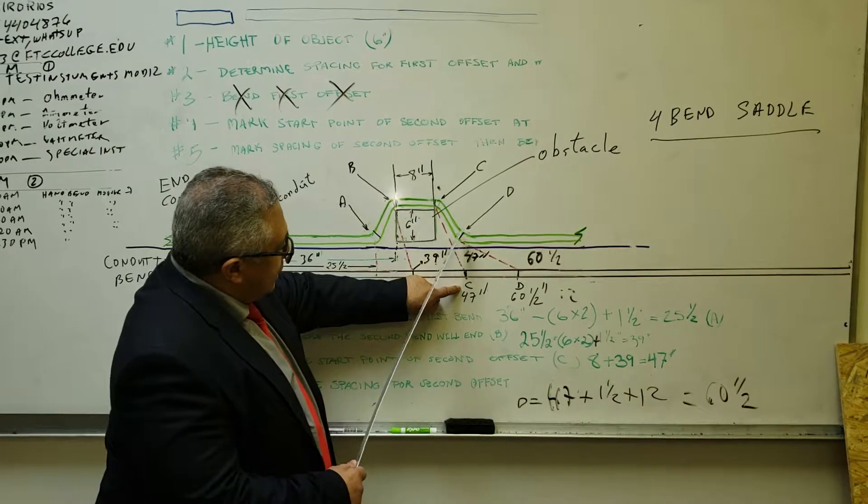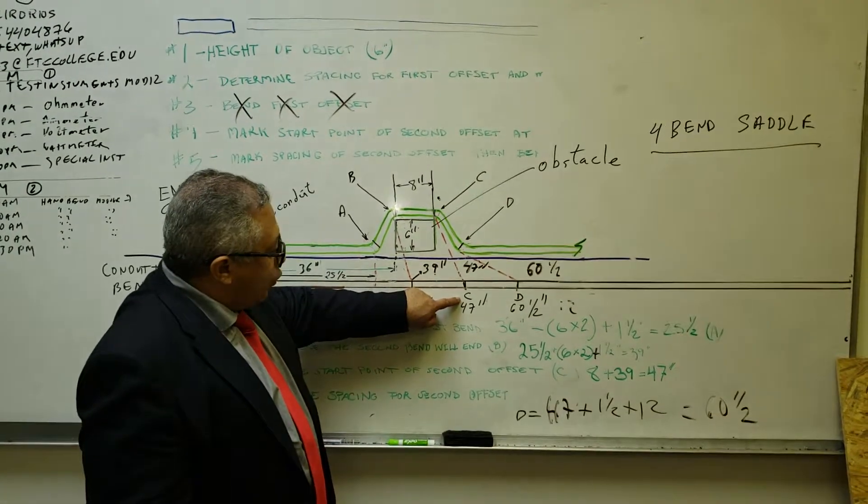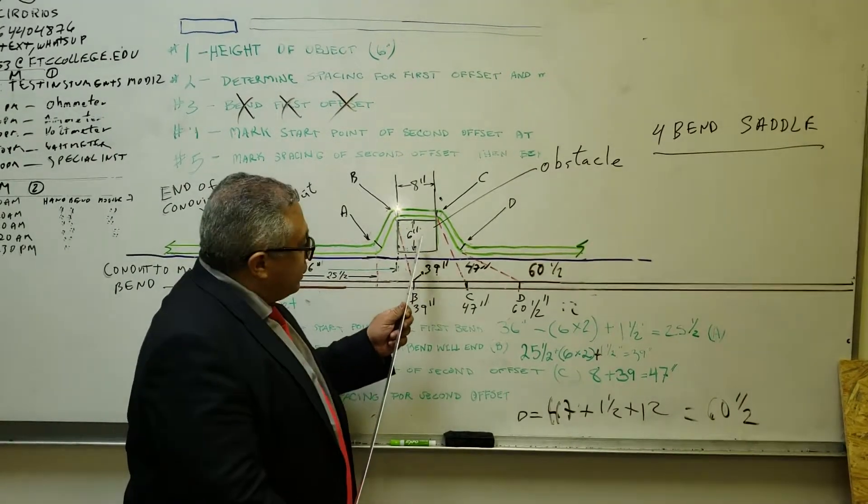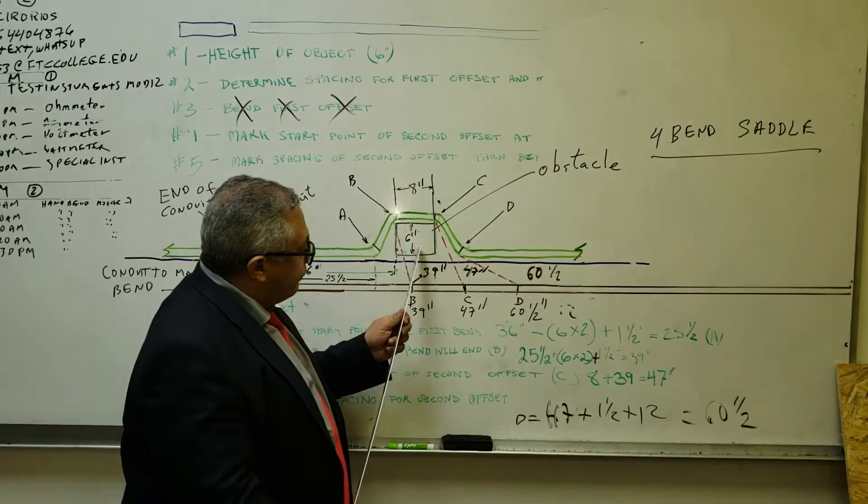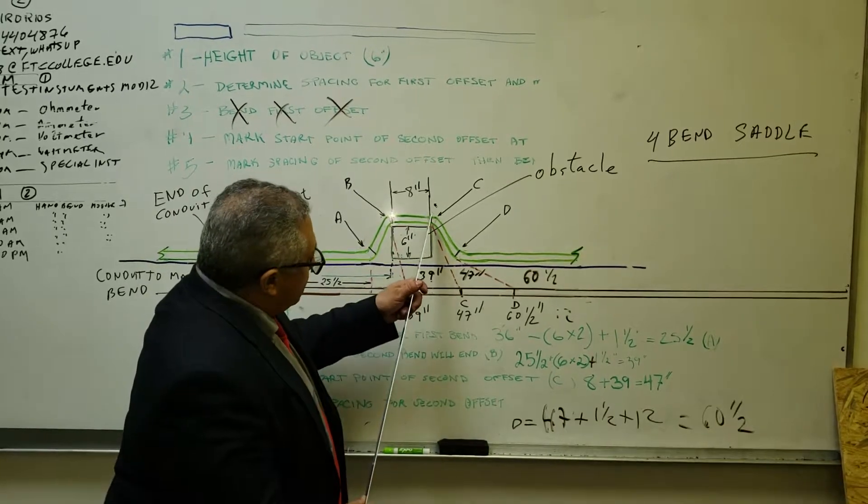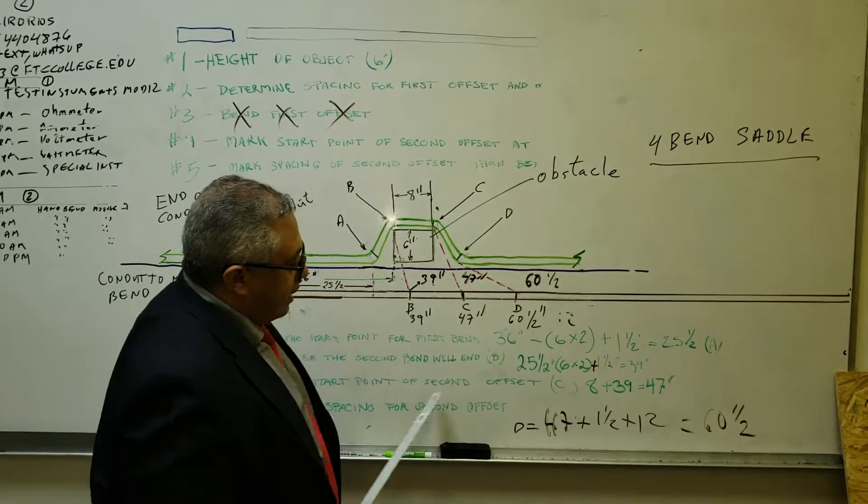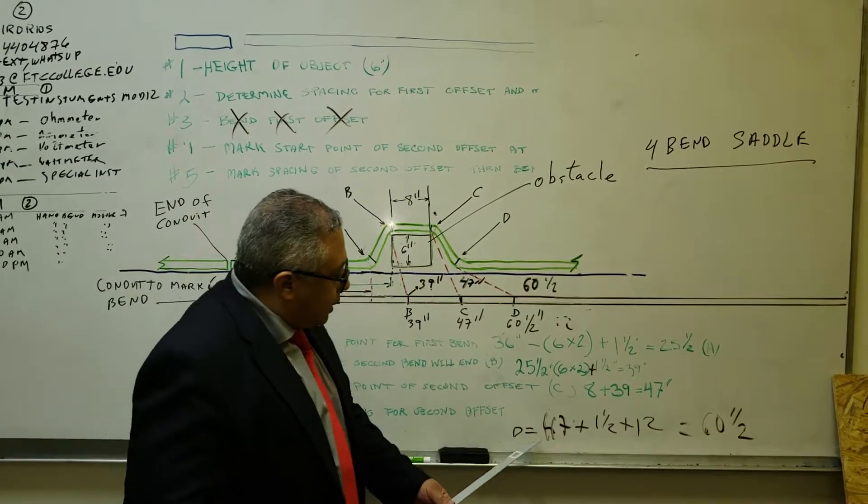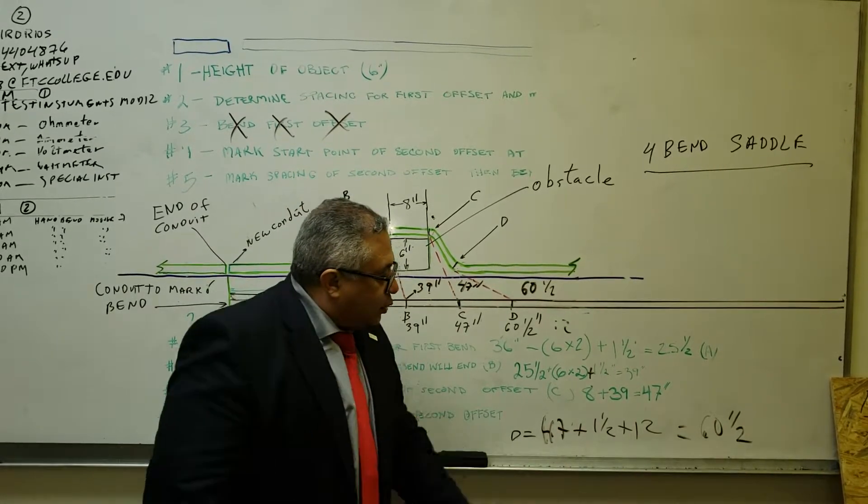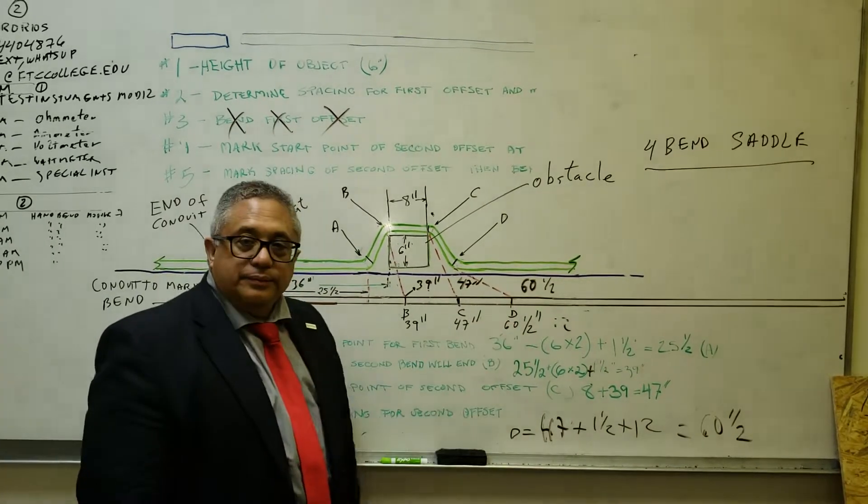Now we need to mark the next point we need to bend the conduit. How do we find that out? It's the multiplier times the height, which is 6 times 2, is 12. 12 plus the shrink value, which is 1 inch and a half. That's how we get 47 plus 1 inch and a half plus 12. That's how we get 60 inches and a half, and then we go ahead and mark the pipe.